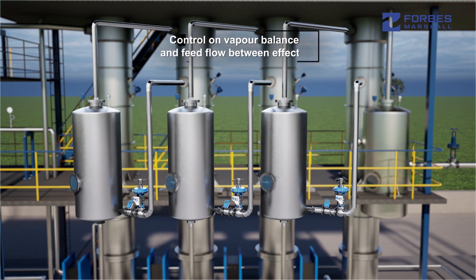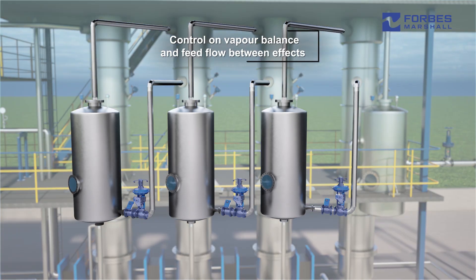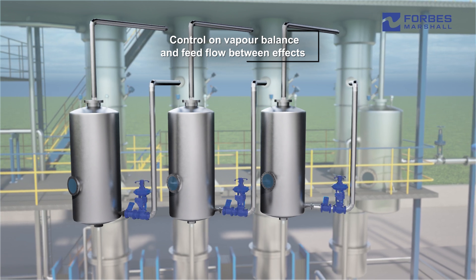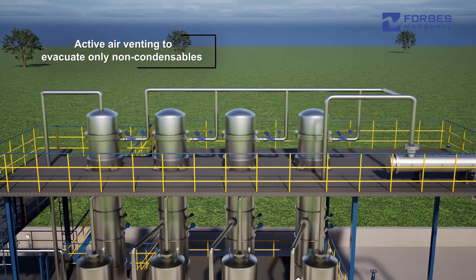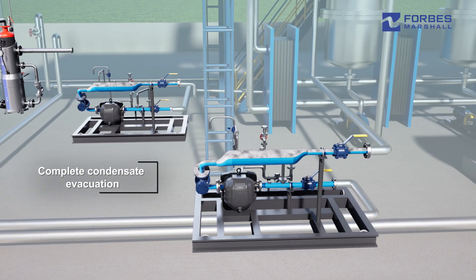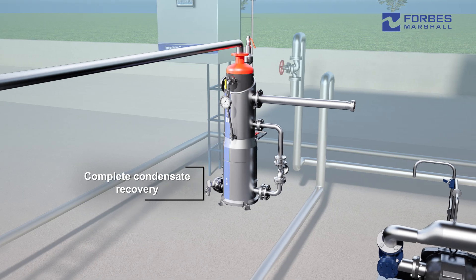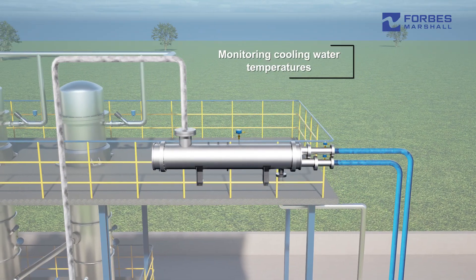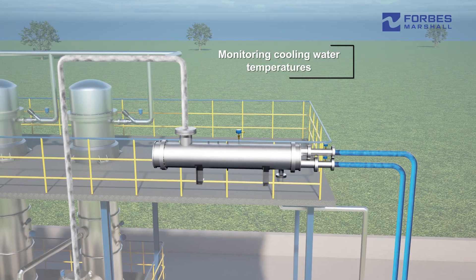Variations in feed temperature are managed by supplementing live steam to the preheater. Vapor balance between effects is controlled through a vapor control valve, while feed transfer between effects is measured and adjusted to maintain a steady state. Active air venting evacuates non-condensibles, and proper steam trapping evacuates condensate, preventing vapor loss and enabling complete condensate recovery.